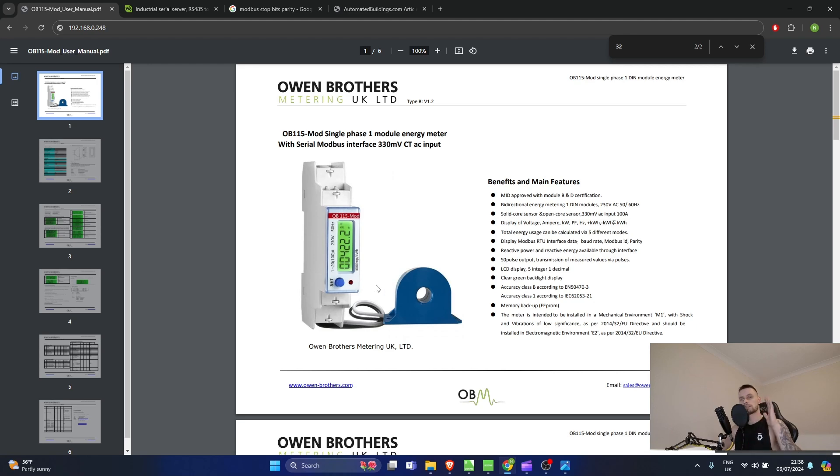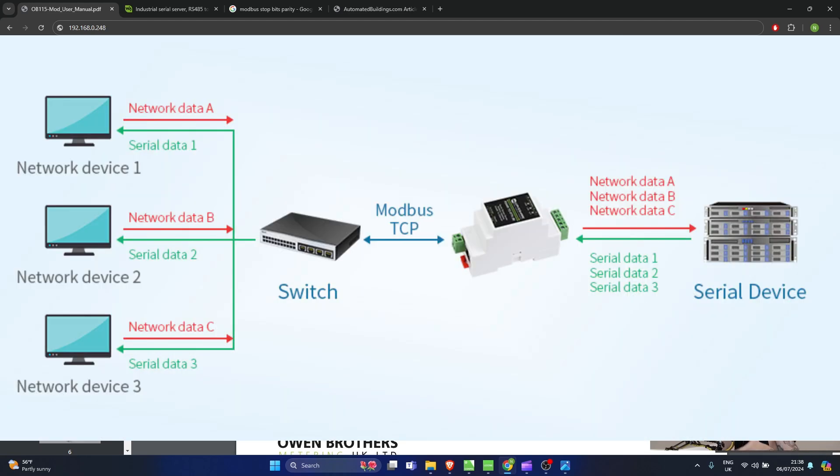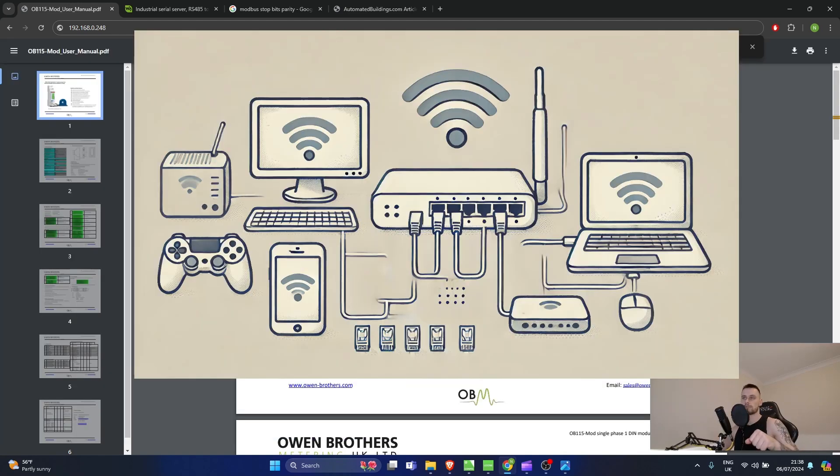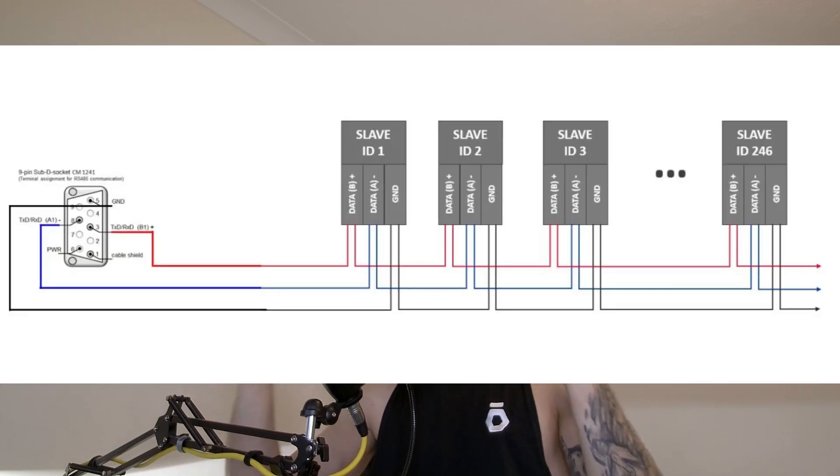What we want to do is translate Modbus RTU into Modbus TCP for the LAN we've established. Why would you want to do that? Sometimes in some installations the Modbus consideration comes at a much later point and there's no longer any opportunity to pull cables to that location. It might be very expensive to dig cables or chase them around, but there might already be a local network established.